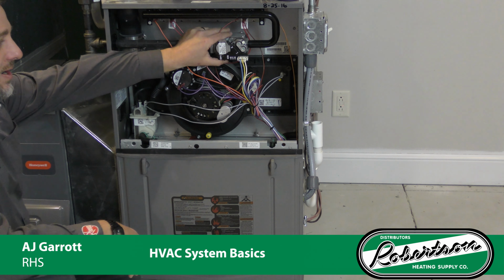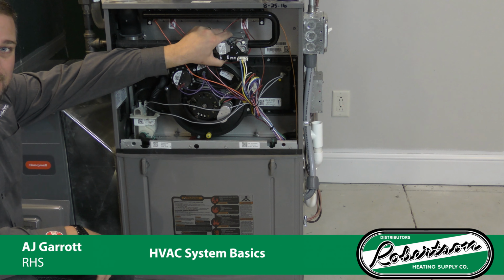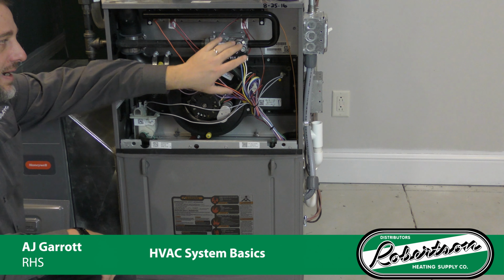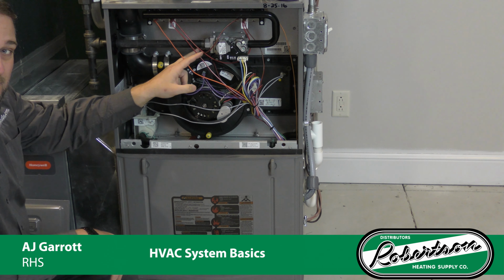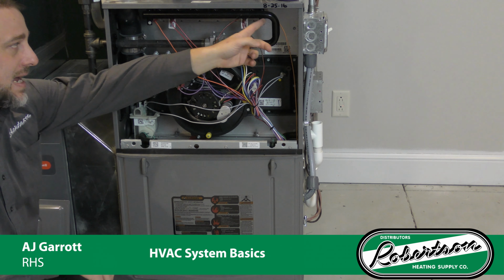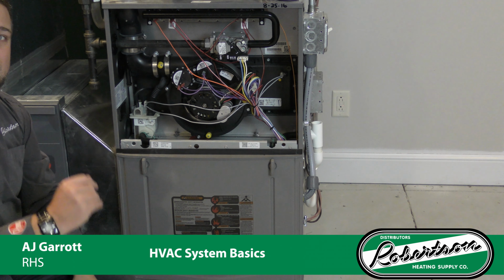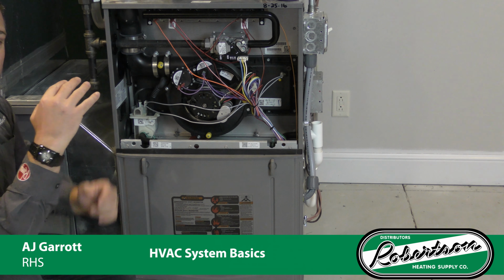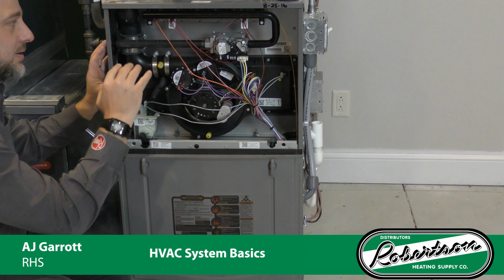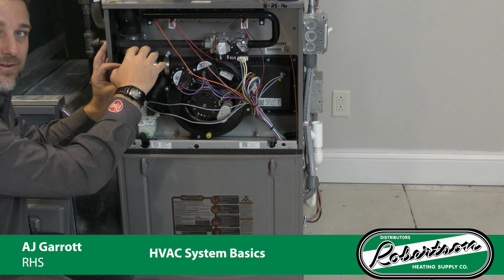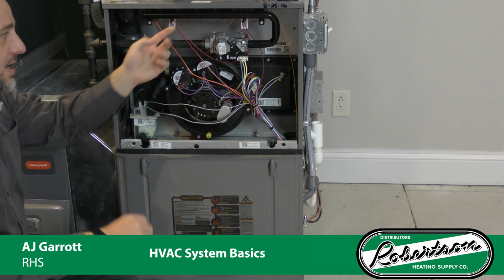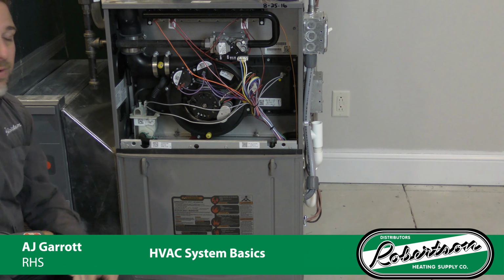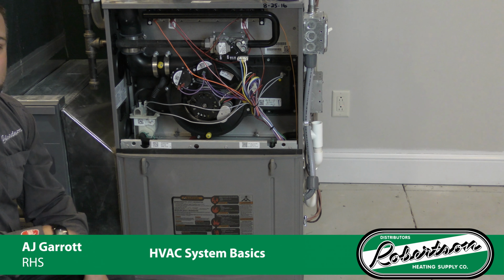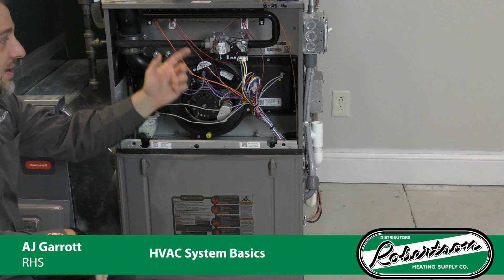Right here, this is actually called a gas valve. Its job is to let gas come from this gas pipe into this manifold right here. The manifold then has orifices inside it that spit the gas out into these burners here and shoots it into the heat exchanger. I'll show you the heat exchanger a little bit later on.